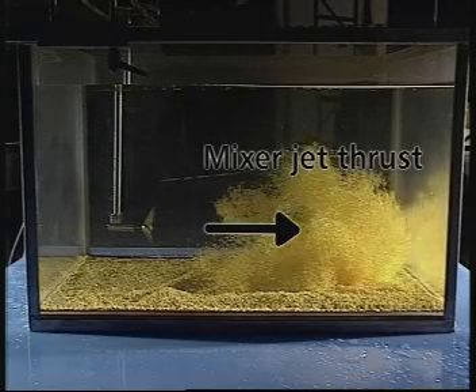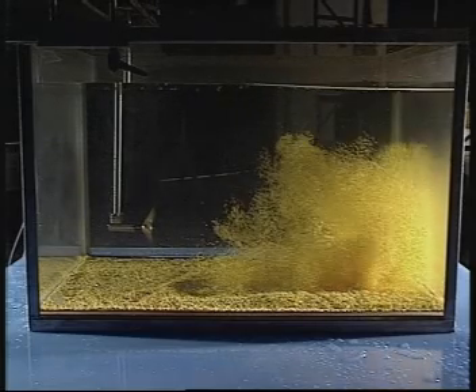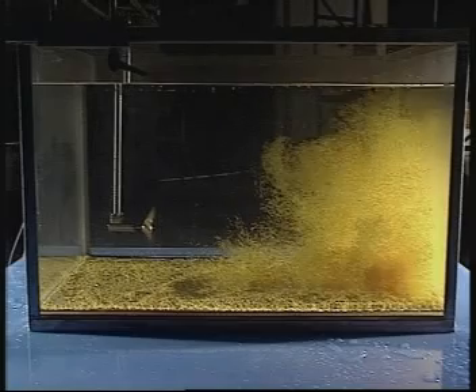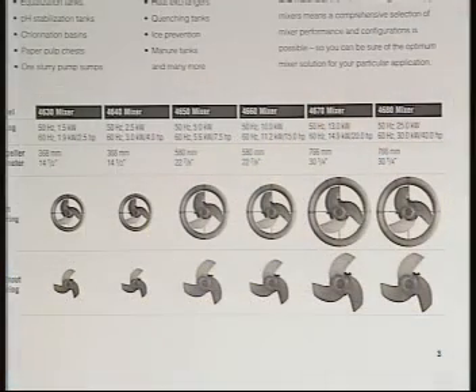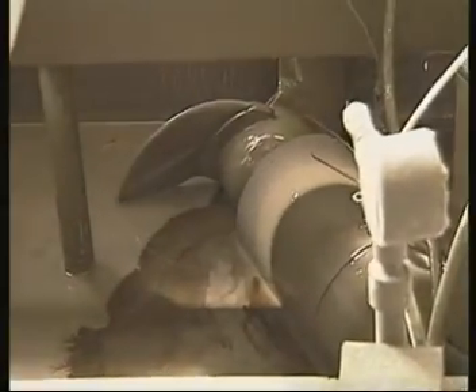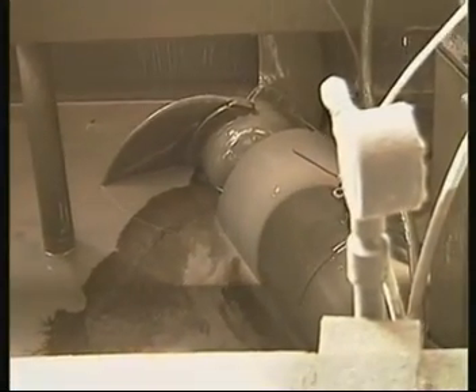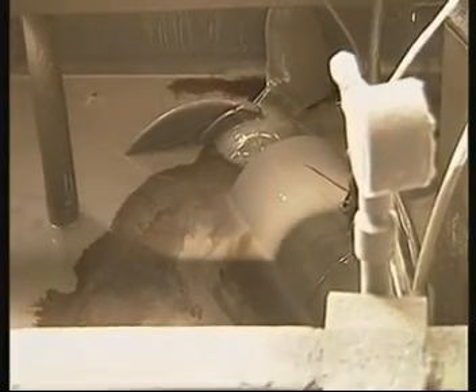A mixer used in drilling mud has to be properly selected for the intended mud by the rig's design engineers to avoid overload. If the specific gravity of the mud is higher than specified when the mixer was engineered by Flygt, it might overload. Thrust is thus not a problem, since it increases with increased specific gravity. It's important that the mixer is always submerged. If it isn't, it'll overheat.